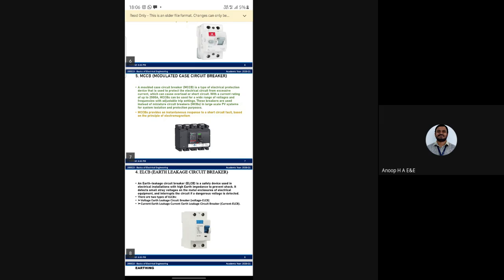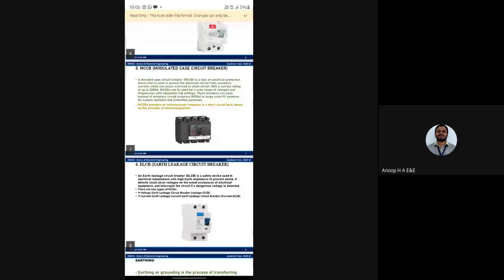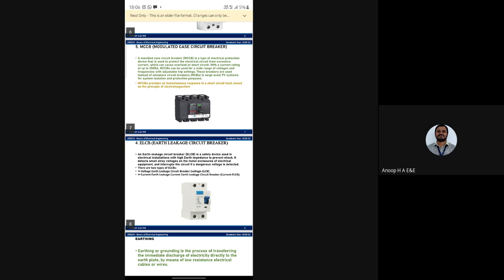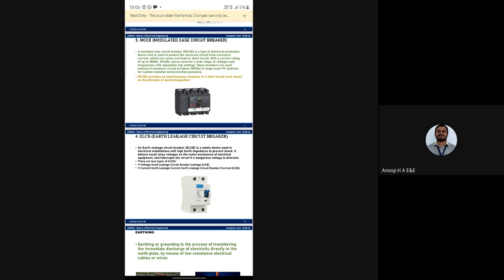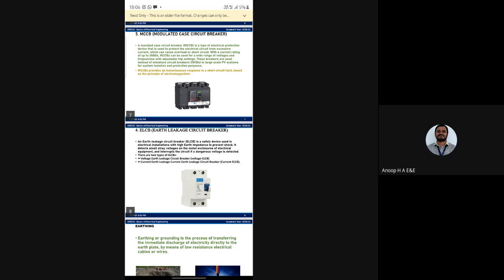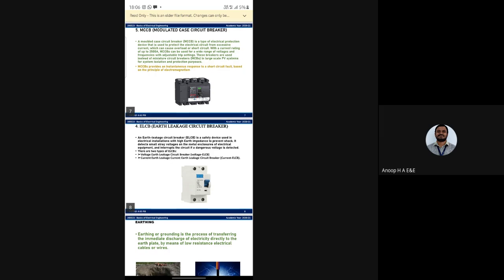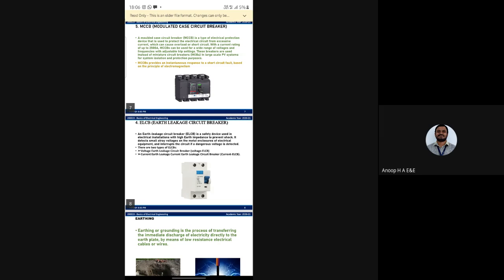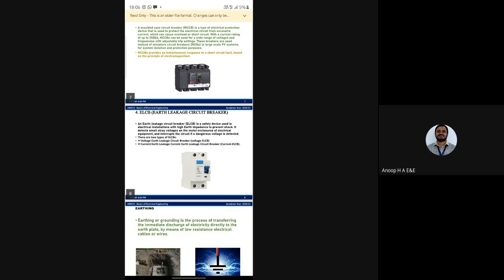MCCB. Full form of MCCB is moulded case circuit breaker. A moulded case circuit breaker is a type of electrical protection device that is used to protect an electrical circuit from excessive current which can be caused by overload or short circuit, with a current rating up to 250 ampere. MCCB can be used for a wide range of voltage and frequency with adjustable trip setting. This breaker is used instead of a miniature circuit breaker, which is basically called MCB, in a large scale system for isolating and protection purposes.